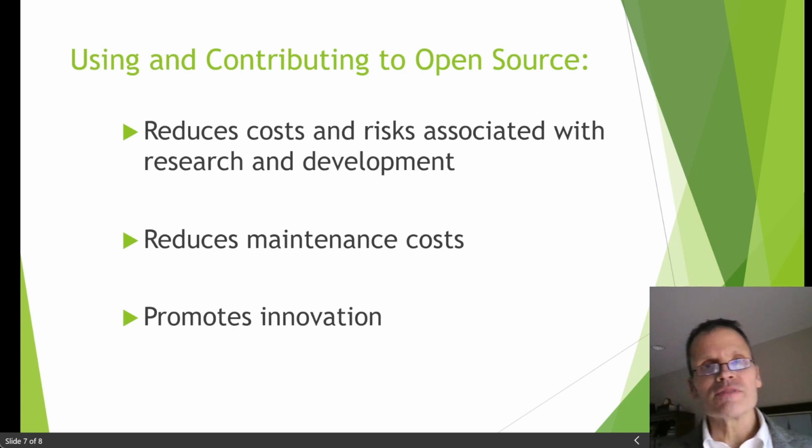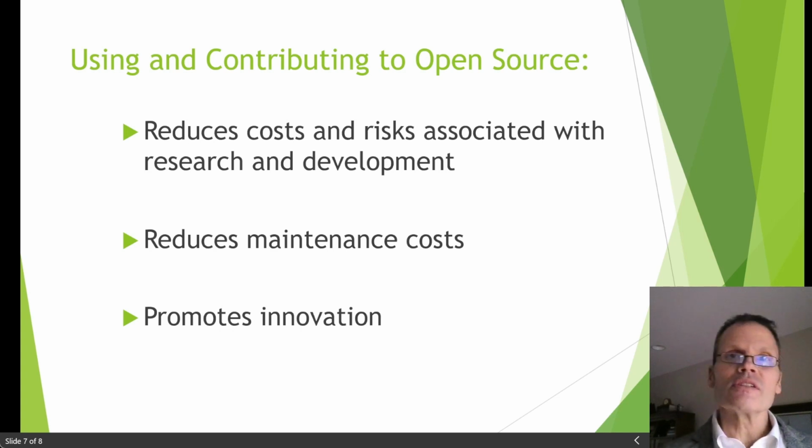And then also within the medical field, you have to go for FDA approval. You can either develop all of your software yourself under whatever guidelines and whatever quality management system you define, or you can treat a large library as software of unknown pedigree, or SOUP, and integrate that large library into your toolkit, into your product, without having to go through the FDA approval process for every component and line of code within that SOUP. And so that open source software becomes SOUP. It becomes software of unknown pedigree that you can integrate and then just test against, saving you, again, a lot of time and risk.